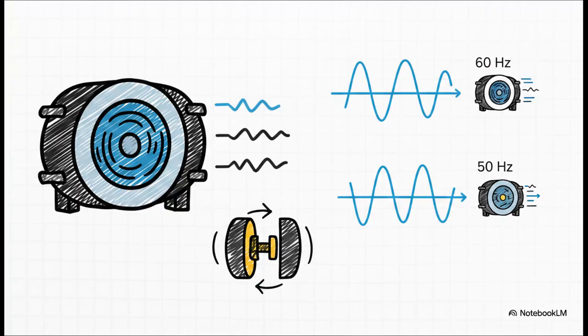So here is the absolute rule of the road for alternating current motors. Their speed is entirely locked to the grid frequency. The synchronous speed of a motor is calculated by taking 120, multiplying it by the grid frequency, and dividing it by the number of poles in the motor. So let's do the math super fast. A standard 2-pole motor on a 50 hertz grid will run at exactly 3,000 RPM.